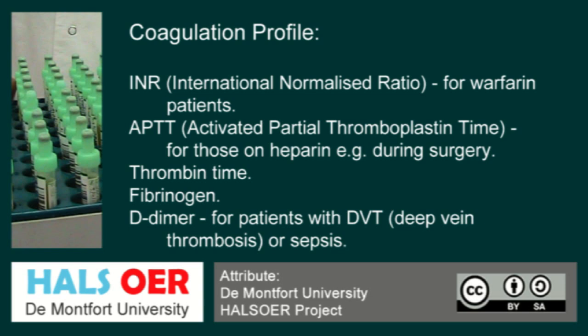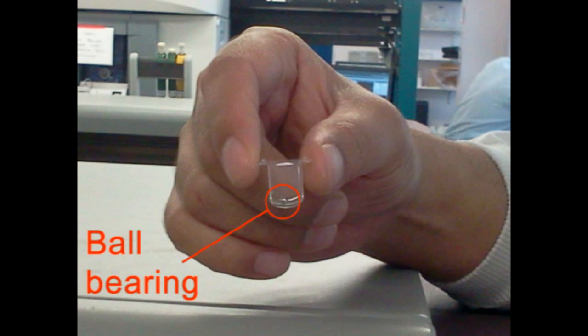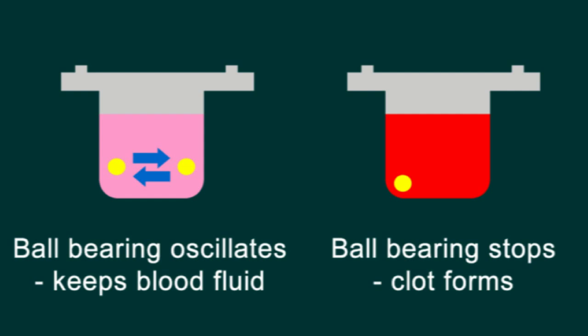What we have here is a little cuvette with a ball bearing inside which oscillates when you send a current to it. Once the ball bearing stops oscillating, what you have is clot formation. What we are doing is identifying clot formation, and that will tell us the end point of the test.